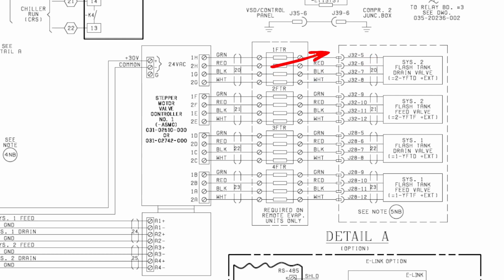And what makes these different is now all of these 4 leads tie back to that 5th common. And so we would give a positive current pulse through green, one step. Positive through red, step 2. Positive through black, step 3. Positive through white, step 4. And then we would just cycle back over again. Pulse, pulse, pulse, pulse. And all of these are coming back to the main common feed on the 5th wire.